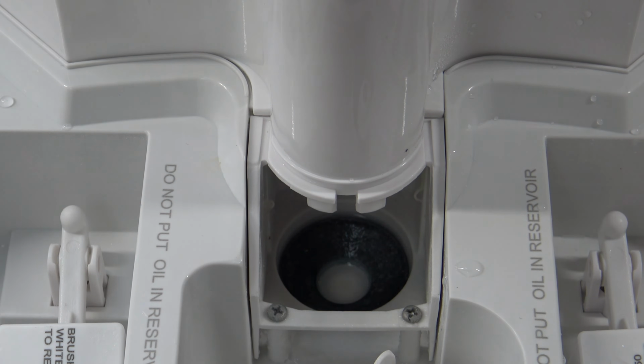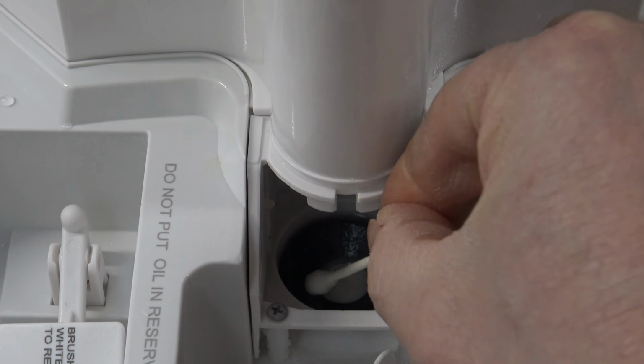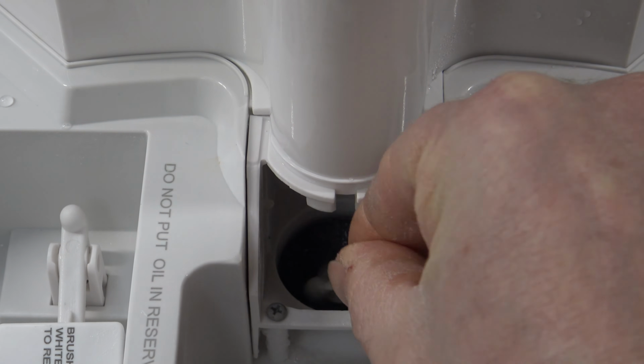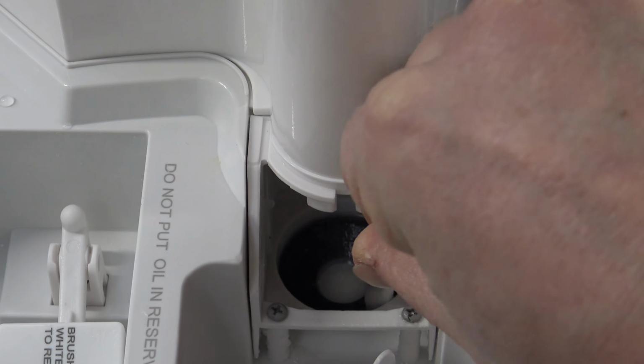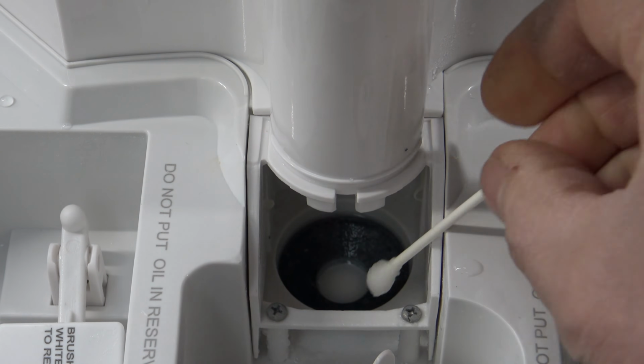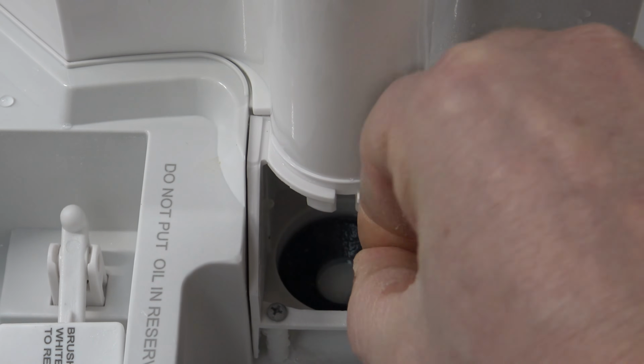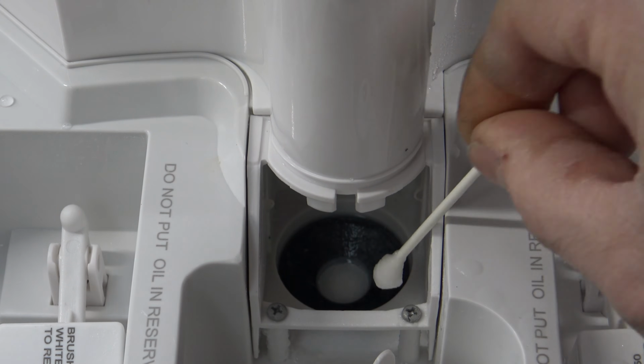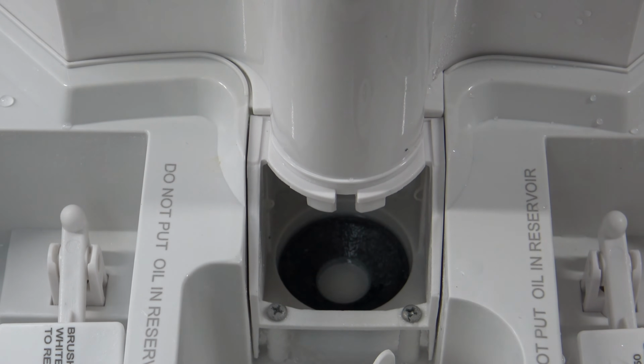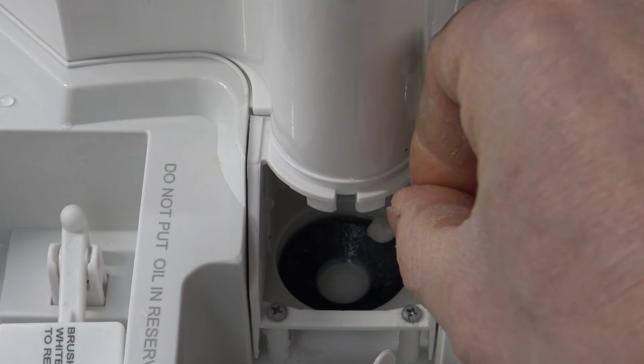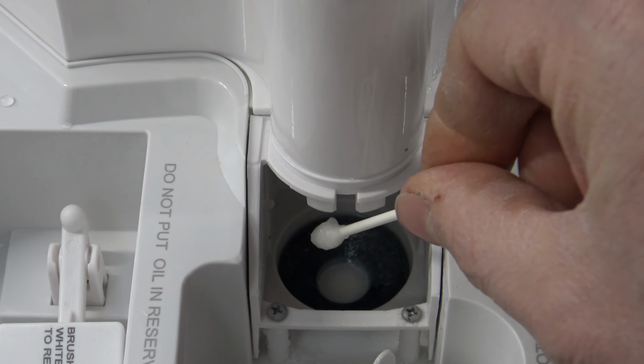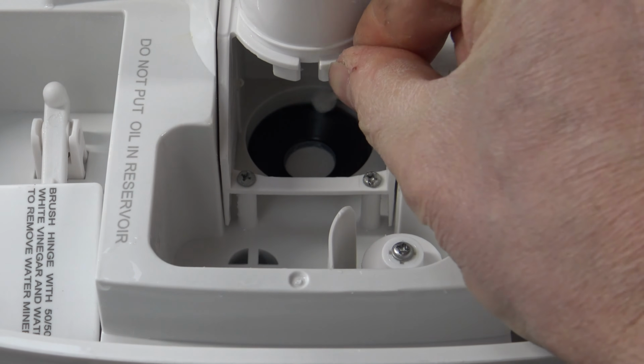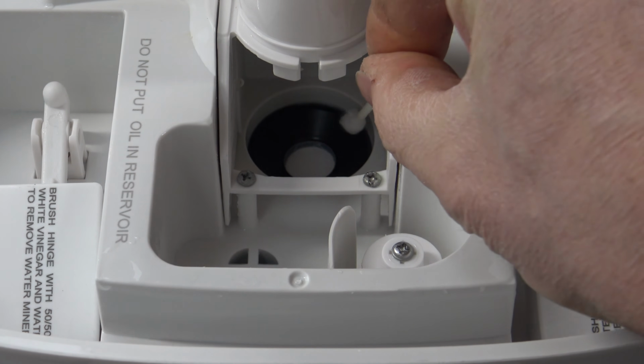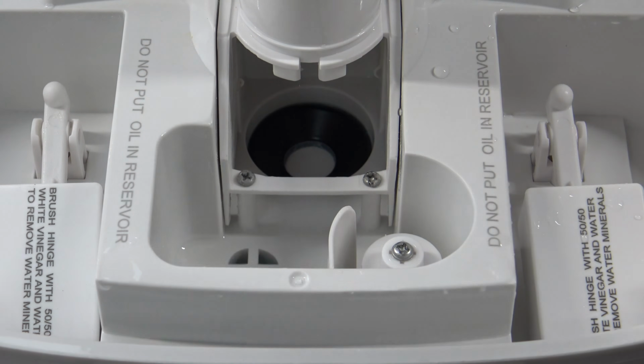Dip your Q-tip in the 50% vinegar, 50% water solution, and lightly rub that black ring until you get all the mineral and calcium deposits off. As you can see, it comes off really easy - you can see right there how it's already nice and black. Work your way all the way around. The transducer is clean when it's nice and black and shiny with no white residue left.